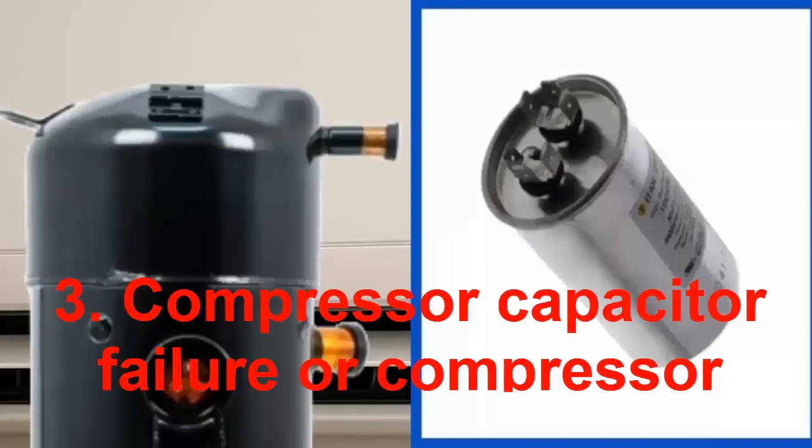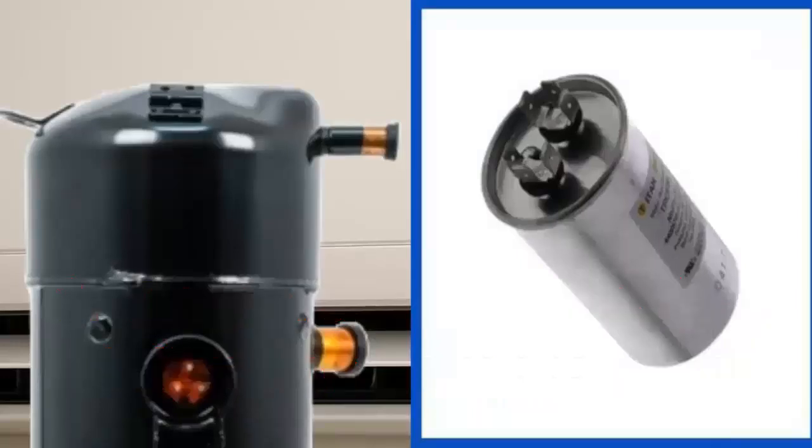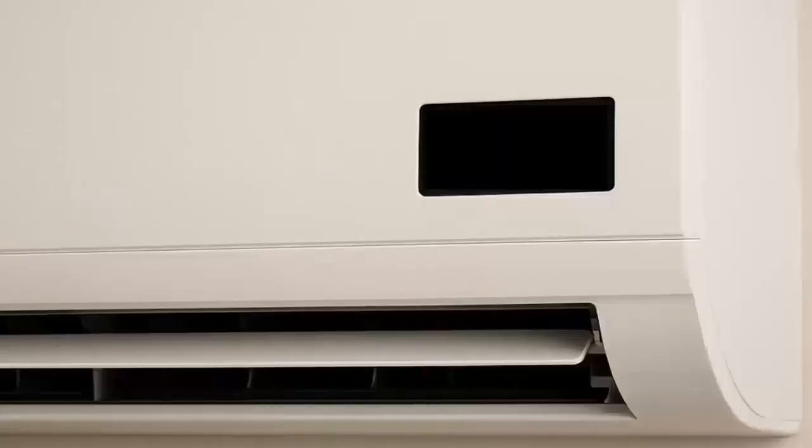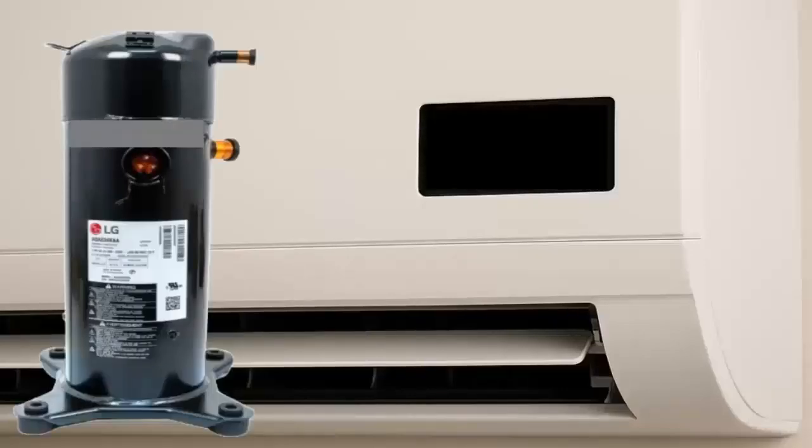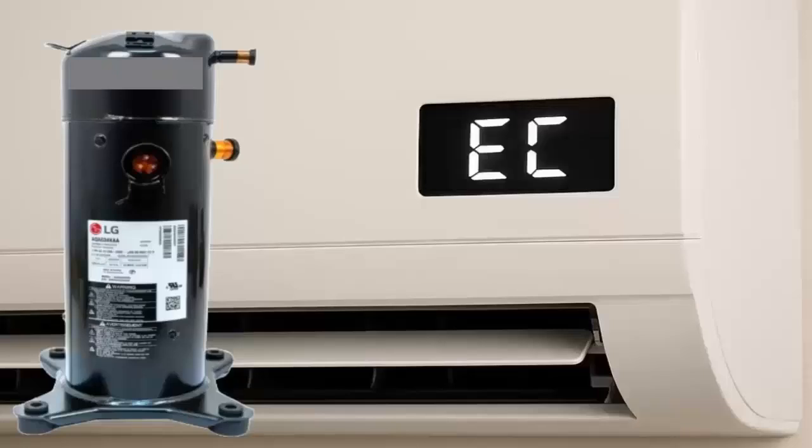Meaning number 3 of code EC is related to compressor or capacitor failures. Another possible cause is a fault in the compressor or its start capacitor. When these components fail, the system can't compress the gas, and cooling stops.